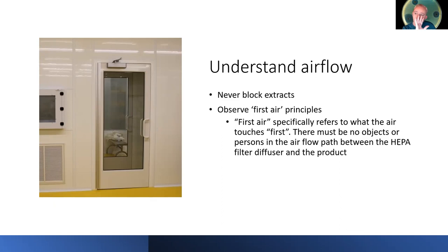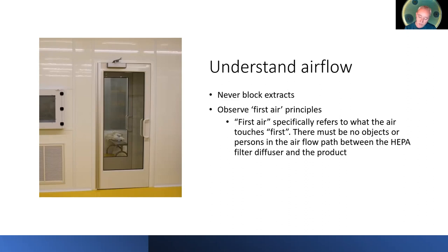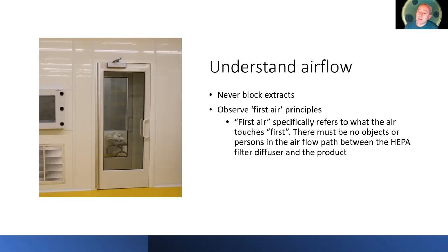Extracts should be the right number, not blocked, and always functional. For unidirectional airflow devices, air comes in one direction at very rapid velocity creating a curtain of clean air. It's important to understand that if an operator needs to interact with that zone and is going to break first air — first air referring to whatever the clean air is touching first — then there should be no exposed product or product vials in the area, or if there is, that batch is deemed reject and the line is cleared. Showing operators airflow visualization programs and what happens when first air is broken is of great importance in training.